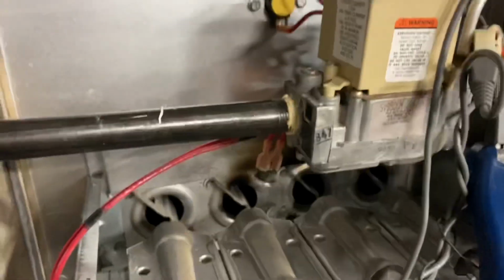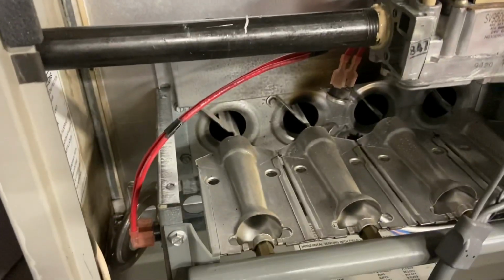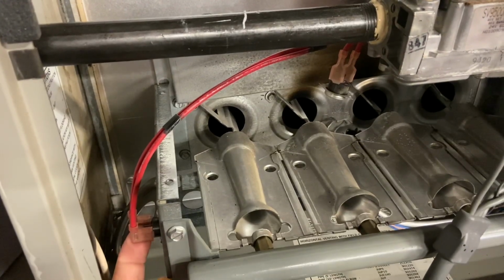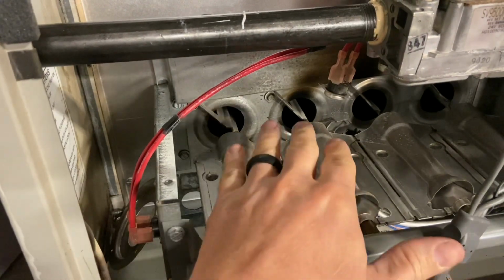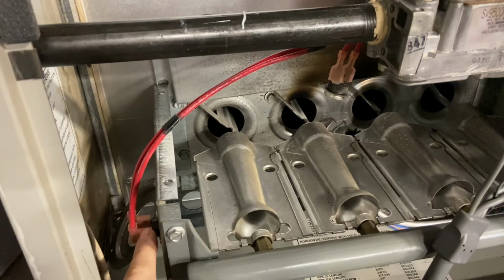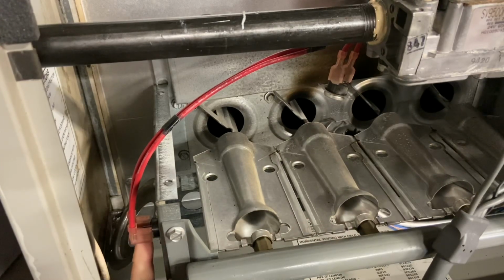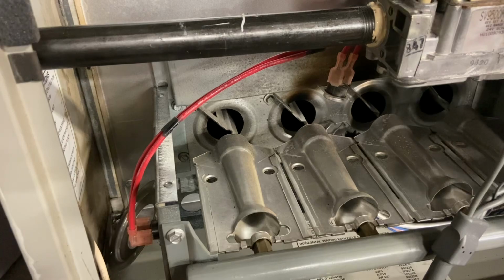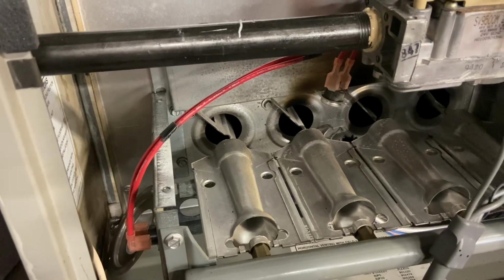There's also another one of these. There's another one of these flame rollouts here on the side and again on the other side. So if the flame rolls out, this limit trips and it shuts it off, and you have to manually come out and press the button to reset it. You don't just reset those, you always want to know why.